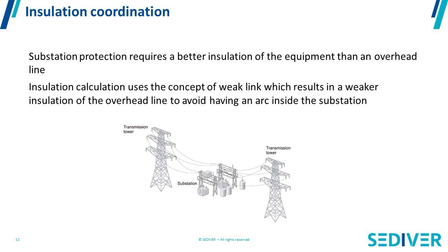So when you design a line and when you try to design the insulation along the line, you define a weak link. If you have an electrical event like lightning, you never want to have an arc inside a substation. By definition, insulation coordination is a set of calculations made by the designer of the line, by which he's going to put the weak link on the transmission line and not in the substation, so that the insulation on the transmission line is lower than the insulation in the substation.